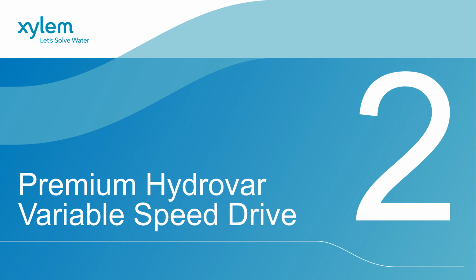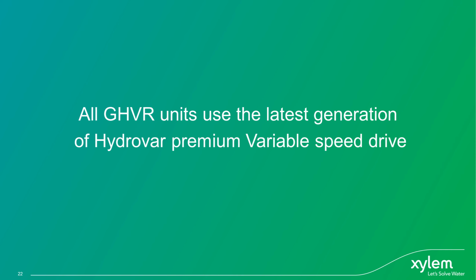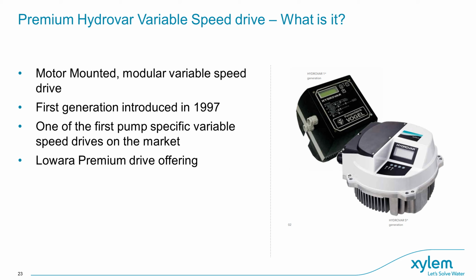Moving on to our second key feature, which is the premium Hydrovar Variable Speed Drive. And just to state, all GHVR units use the latest generation of Hydrovar Premium Variable Speed Drive. So, just a brief introduction into the Hydrovar. It's our motor-mounted, modular variable speed drive. It was first introduced in 1997 and one of the first pump-specific variable speed drives on the market. Other drives were available at that time. However, the Hydrovar was one of the first drives dedicated to a pumping system, rather than a universal, multi-use, multi-application drive.